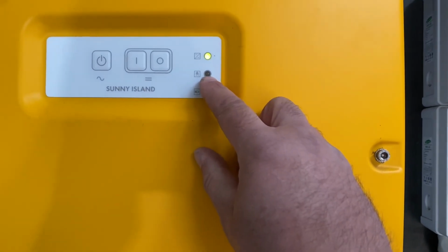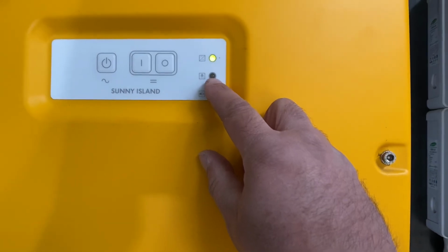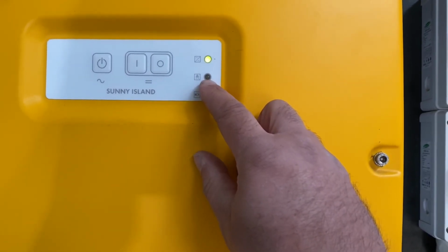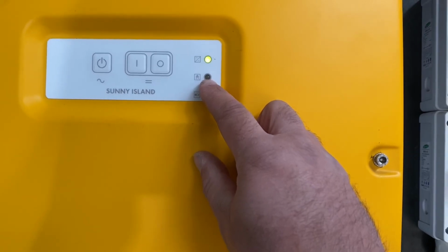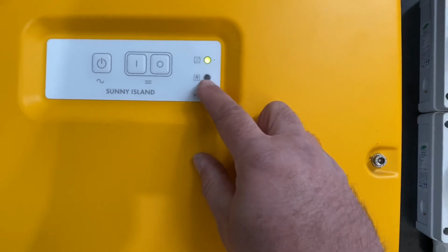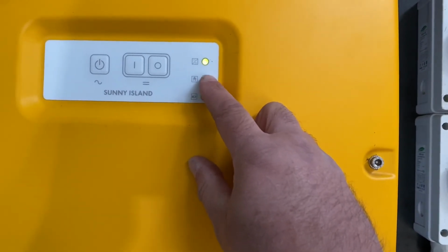Generator amber light means the generator is on but is not synchronized and not delivering power yet. When it turns green, the generator is synchronized and delivering power. When it is red, the generator is not in tolerance. The frequency is too high or too low, or the voltage is too high or too low.